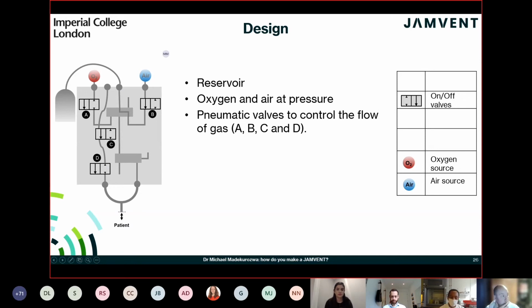In high-end ventilators, these are typically actuated solenoids that change their diaphragm. So they're not just on and off; they actually change the size of their diaphragm. So this means that they're specialist components, a little bit difficult to source, which puts a bottleneck into the supply of ventilators. We opted for on-off solenoids, which makes the design a little bit more difficult to make, but it makes it more readily available.